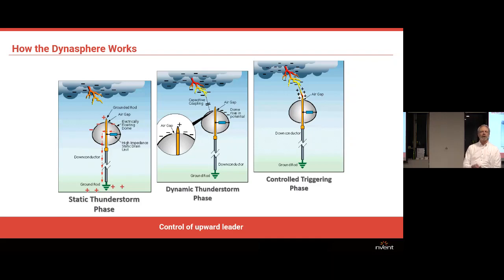So the Dynasphere works by having an earth central point and a sphere around it, which is isolated from that central point. That is coupled to the charge building up in the cloud, and there's a discharge network built into there, a resistor and possibly a capacitor. And so that allows it to build up the charge so that it launches the upward leader that I was describing earlier at exactly the right moment that the lightning was ready to form anyway. That way, this is not creating lightning when it's not necessary, and it becomes the preferred path for the lightning strike.